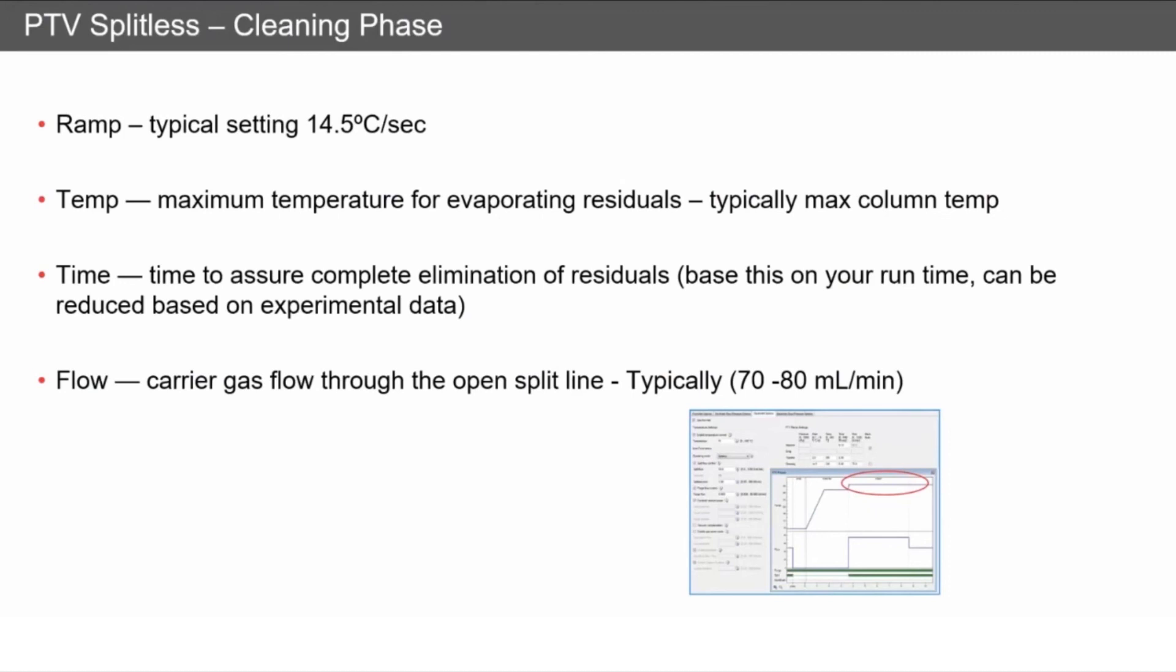The flow—this is the carrier gas flow through the open split line. You want this to be high, encouraging all of these non-volatiles to leave your inlet. Set this to around 70 to 80 mL per minute.